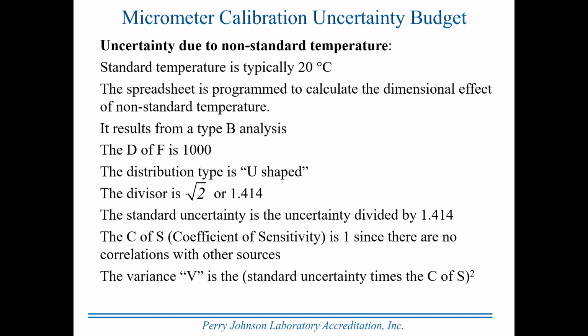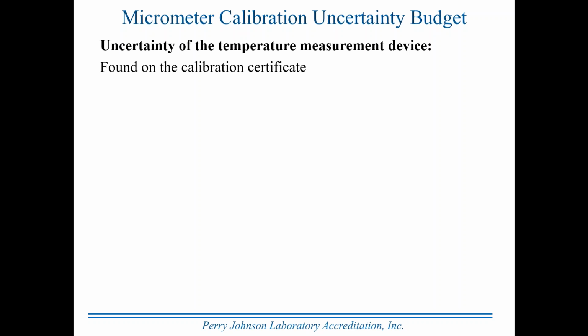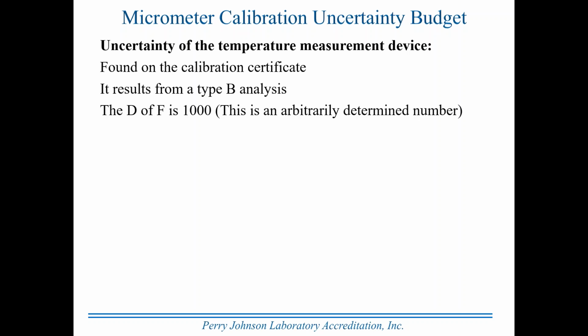And the variance is the standard uncertainty times the coefficient of sensitivity, that product raised to the second power. You'll get tired of hearing that here shortly, I'm sure. Uncertainty of the temperature measurement device. Remember, we get that information for a calibrated device. We get that off the calibration certificate. It results from a type B analysis. Degrees of freedom is 1,000. And again, as stated previously, it's an arbitrary number.